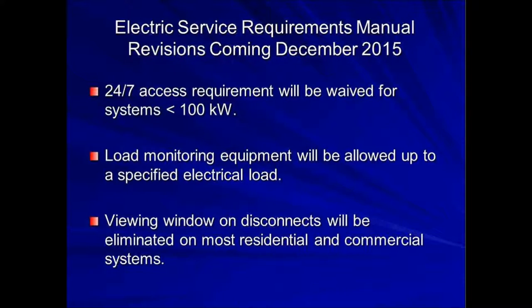That means the 24/7 rigid access requirement we had before for any cogeneration system is not going to be there anymore. It's just going to be what we consider readily accessible. So in a meter room or something, we don't have to have all the switches on the outside anymore. If it's a residence, we wouldn't have the customer cut a hole in their wall to make a gate because that's the only way in. It's just readily accessible, as long as we can get to the meter, that's good enough.